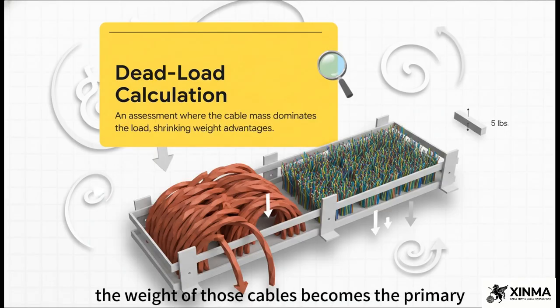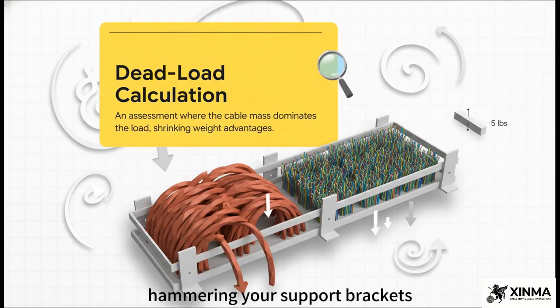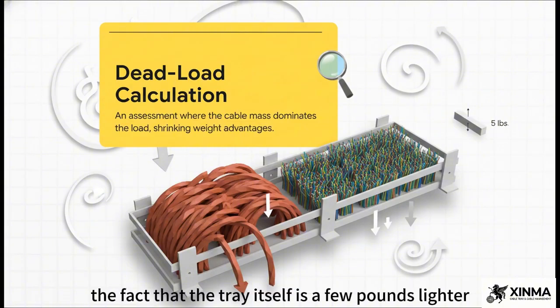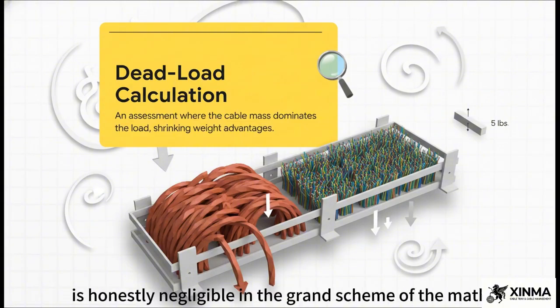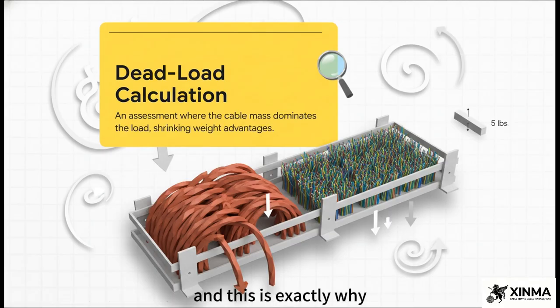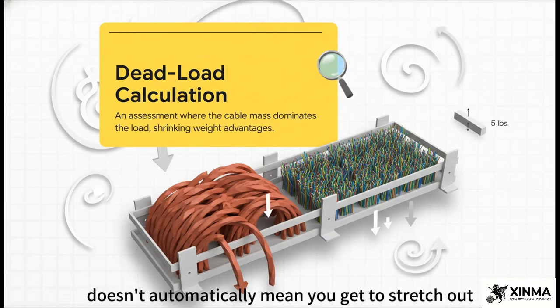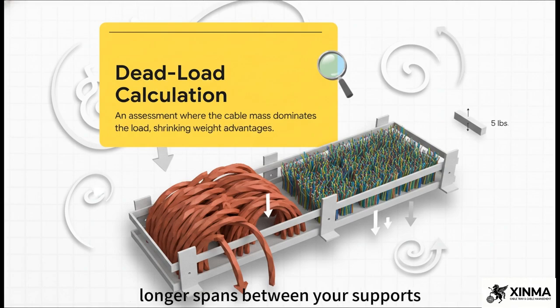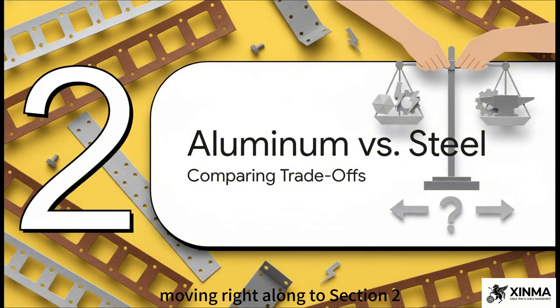The weight of those cables becomes the primary downward force hammering your support brackets. The fact that the tray itself is a few pounds lighter is honestly negligible in the grand scheme of the math. And this is exactly why a lighter tray doesn't automatically mean you get to stretch out longer spans between your supports. Moving right along to Section 2, aluminum versus steel.